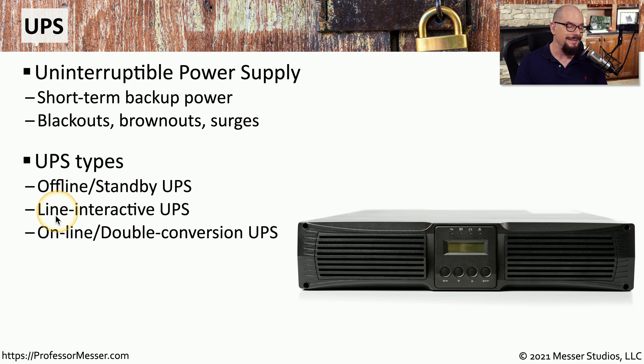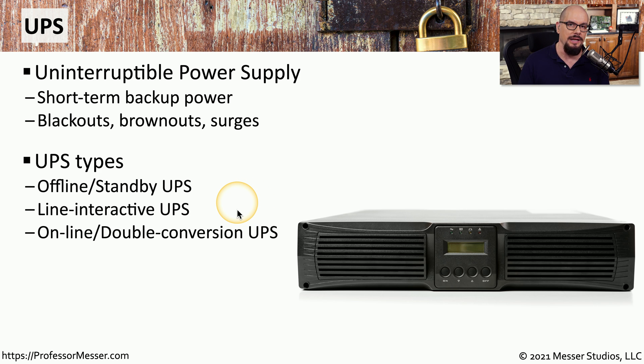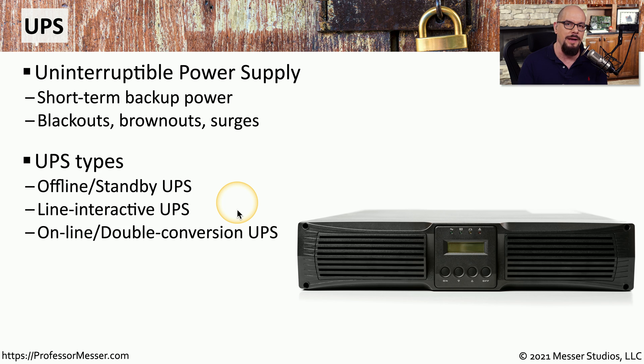Another type of UPS is a line-interactive UPS. If the voltage is slowly diminishing on the line, the UPS can slowly ramp up the amount of power being provided by the batteries. So during brownouts or times when the voltage is not at optimal levels, the line-interactive UPS can fill in the differences from the power source.